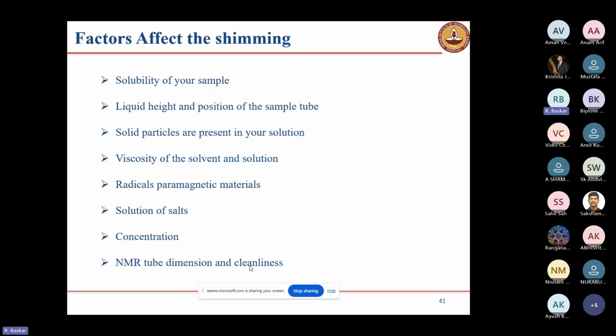Once we have given the proper acquisition time, then we have to choose the proper spectral width, because sometimes signals appear in the negative region or positive region apart from the general spectral width. At that time we have to increase the spectral width. So we have to choose the proper spectral width. This acquisition time, I told you, is related to the total data points. If you are giving more acquisition time, we will get more data points, I mean TD, total data points. So it will take a lot of time, but we will get a high quality NMR spectrum.